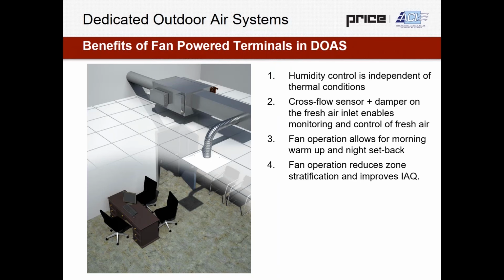As well, fan operation reduces zone stratification and improves indoor air quality. So when we're looking at temperature deadband, we can keep that fan generally running quite high, even when we look at Washington State Energy Code and 0.12 watts per CFM, we can keep those airflows quite high, which is going to mean that the zone is going to be less stratified. In the actual occupant zone, in the breathing zone, we're going to find the temperature there is going to be realistic for what the thermostat's reading.